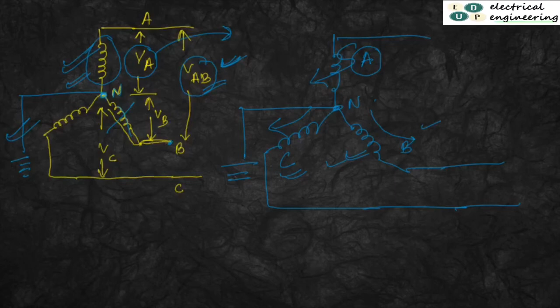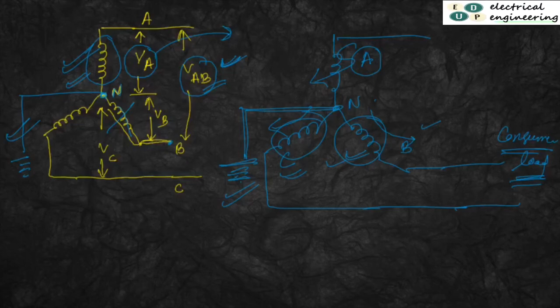Okay, and it can also damage the winding, since such a high voltage and current will be very high. So by providing the grounding path, it will divert all the current due to surge voltage or lightning strike to ground, discharge all the current to ground, and by doing this it can protect the transformer winding as well as your consumer load. So these are all advantages of doing your neutral grounding.